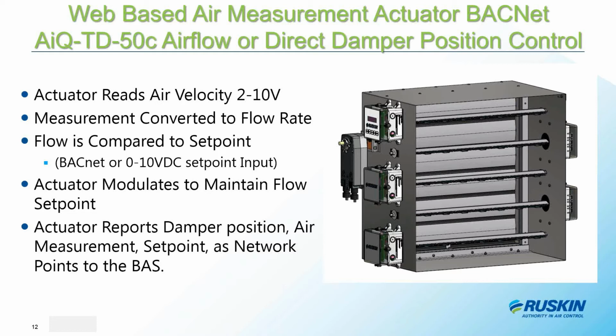Using the BACnet interface, you can toggle from flow control to direct position control. And direct position control just allows you to command the damper full open or full closed or to any position really that you're looking for in place of providing it a CFM set point. So our normal mode is flow control, and we're looking for a CFM set point. The position control would be used for building purge operations and to drive the damper closed when the fans are off or when the building is unoccupied. It becomes a BACnet interface position control damper via BACnet MSTP or BACnet IP interface.